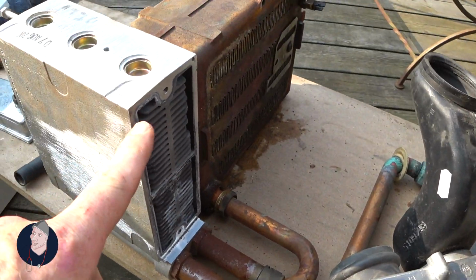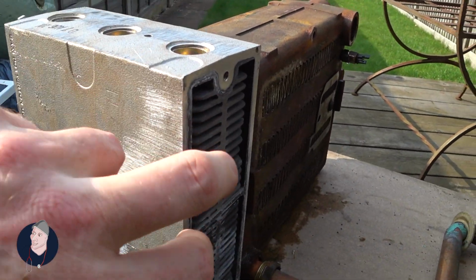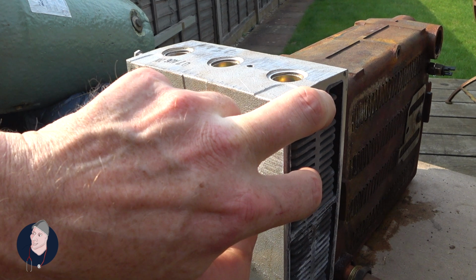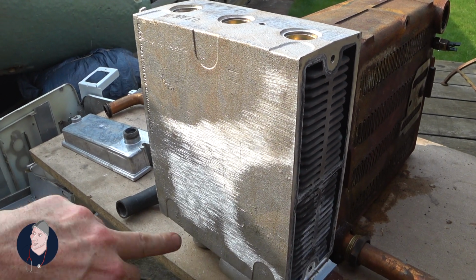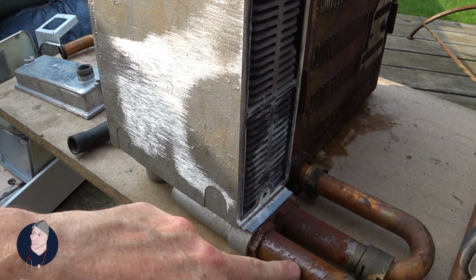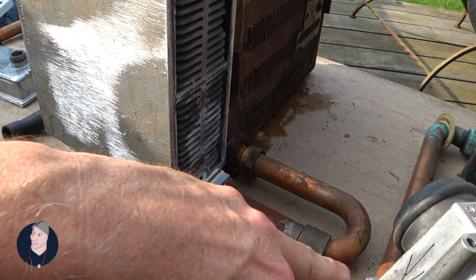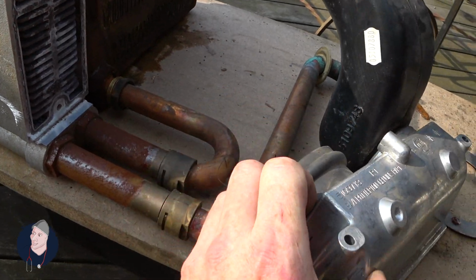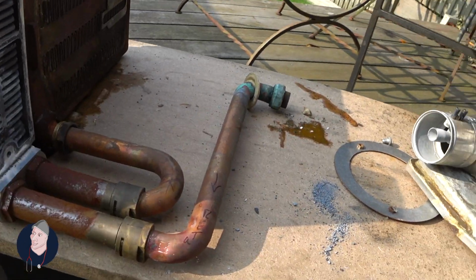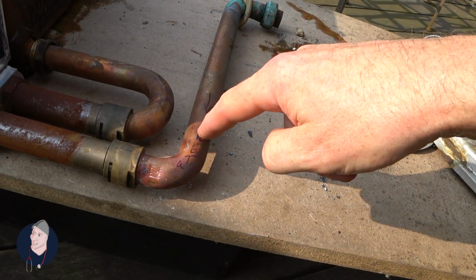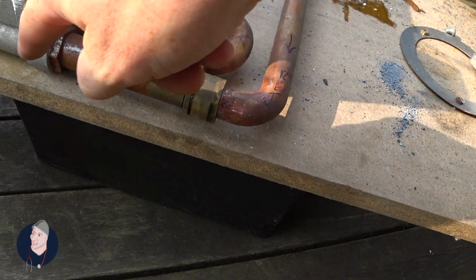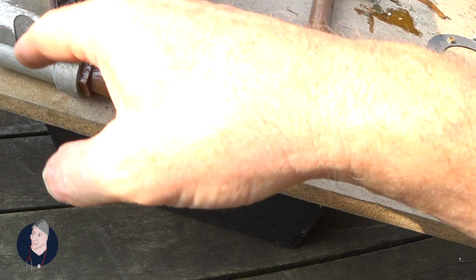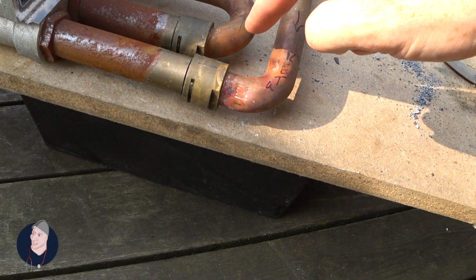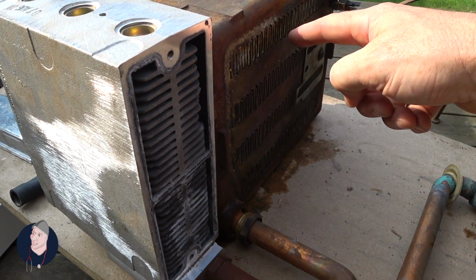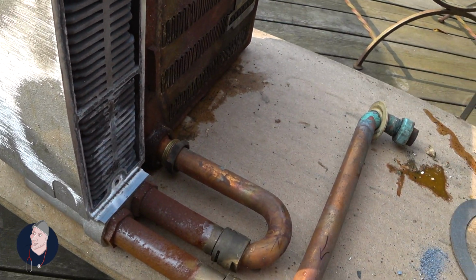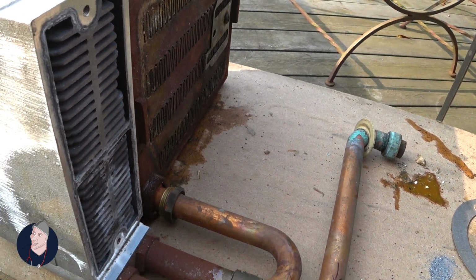So meanwhile, if you imagine this is getting warm inside of here, inside of here is a coil of the flow and the return. So if you imagine the return pipe from your central heating is coming back through here, the cooler temperature out of your heating system goes through here, the heat from here is dissipated back into this and then sent back into the heat exchanger to be heated up and back out the flow pipe.